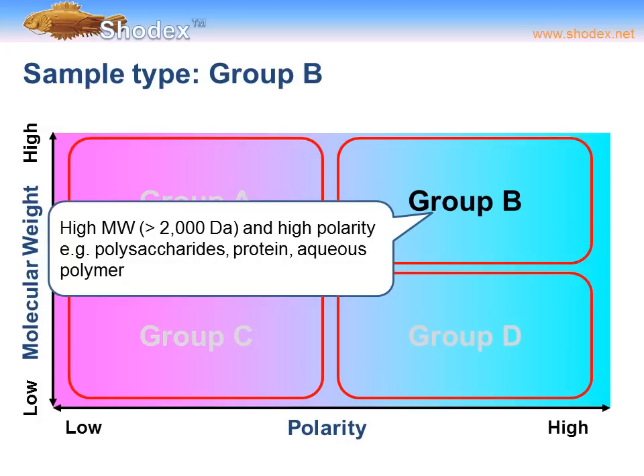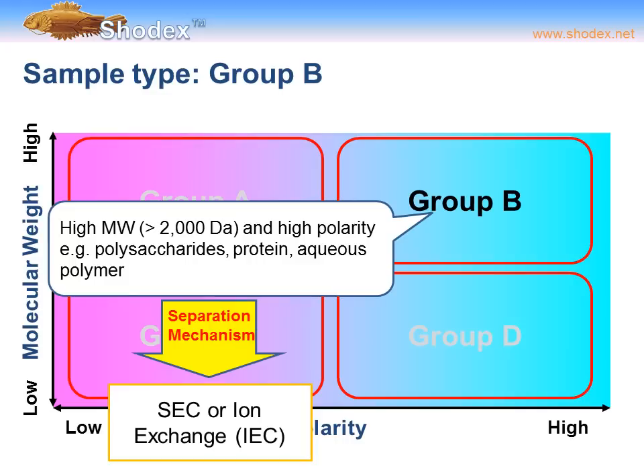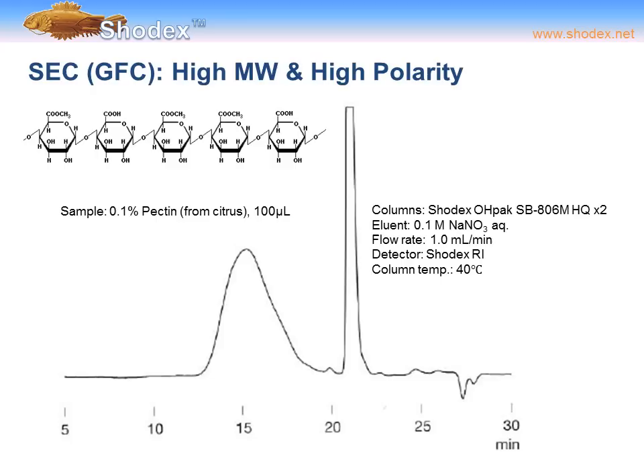Sample type group B comprises high molecular weight, high polarity compounds — most often above 2,000 Daltons. Examples include polysaccharides, some proteins, and aqueous polymers. The separation mechanism is size exclusion or ion exchange (IEC). We use the term GFC — gel filtration chromatography — instead of GPC because in this case we use an aqueous solvent, since the high molecular weight compound is also of high polarity and dissolves in water.